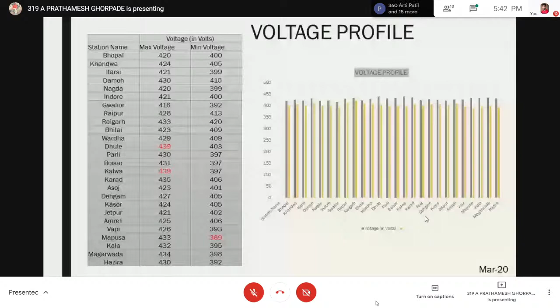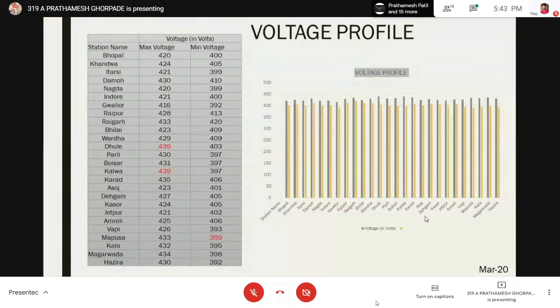Then, as we see the frequency profile, we also analyze the voltage profile data of various stations. There are 26 stations available at Western region, in which we get the maximum voltage at the Dhule and Kalwa station and the minimum voltage at the Mapusa station. As we know, for the three-phase supply, voltage is 415 volt, which is the standard value, and in that 6% means 390 volt to 440 volt, the voltage is acceptable. So we conclude that the system is good if the supply voltage varies between 390 to 440 volt.